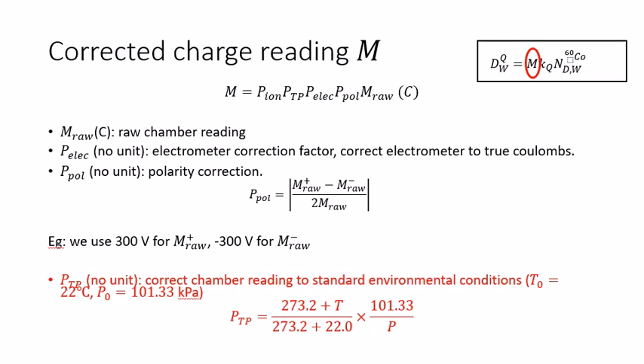The second factor is PTP, the temperature and pressure correction factor. The reason we need to correct the temperature and pressure is because the ion chamber we used for TG51 is not sealed. So the chamber reading is affected by the temperature and pressure from the outside environment that the chamber is placed in.